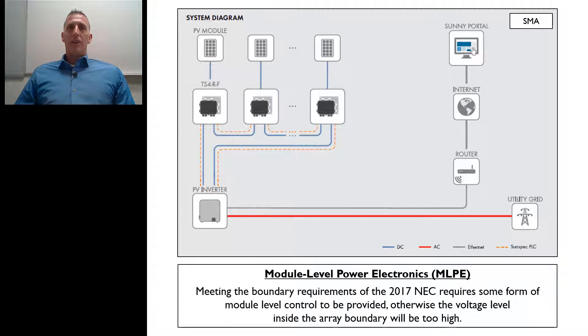Remember, the voltage levels outside the array boundary, 30 volts or less within 30 seconds. But the voltage levels within the array boundary, those are 80 volts or less within 30 seconds.